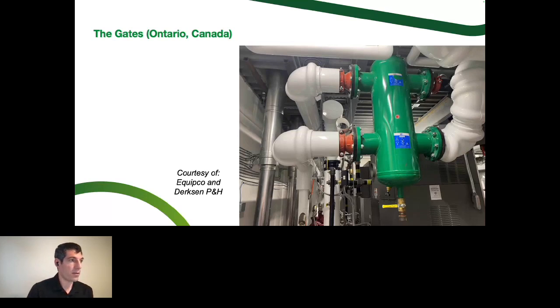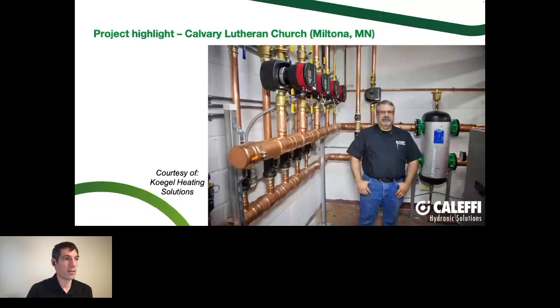Another example here, a lot of different ECM circulators going out to the building. I think this was a geo system, and we've got all the flow meters coming back here. So in this case, you would be able to just pull the pin of this flow meter, this quick setter valve, and see what the flow rate was and verify that that's matching the circulator, and also that you're properly separated there. You shouldn't see any GPM on any of these flow meters if this boiler is on and these circulators are off over here.